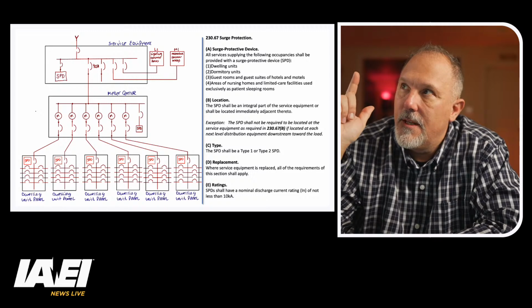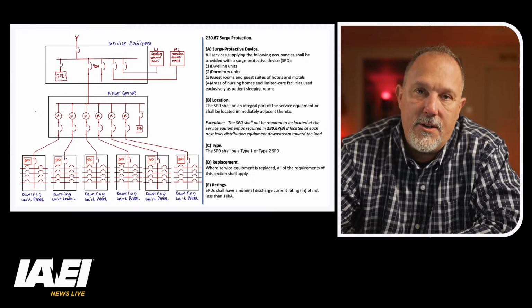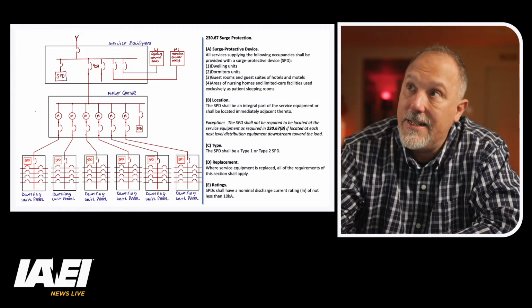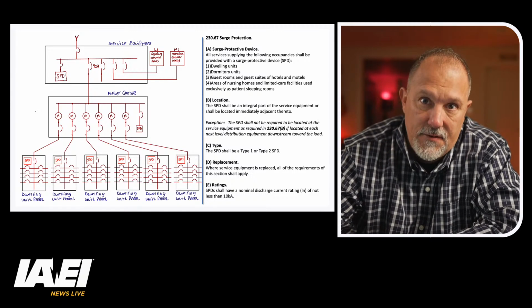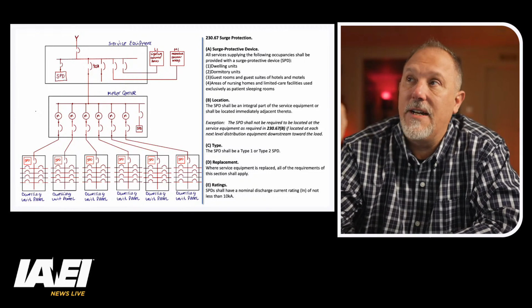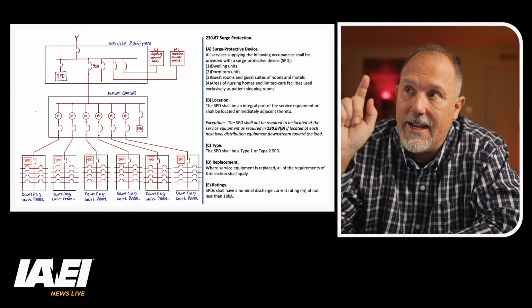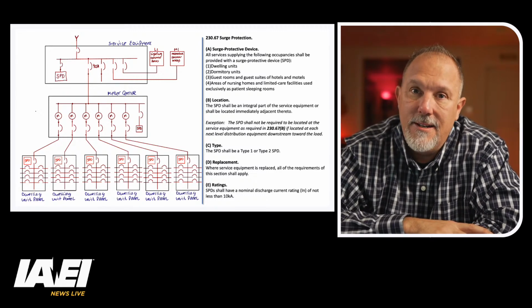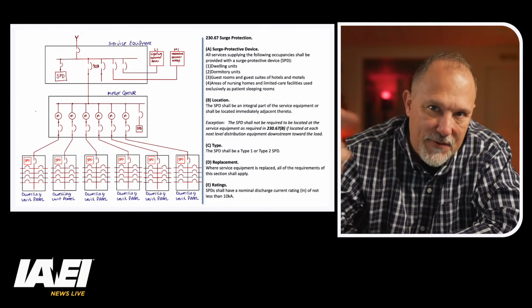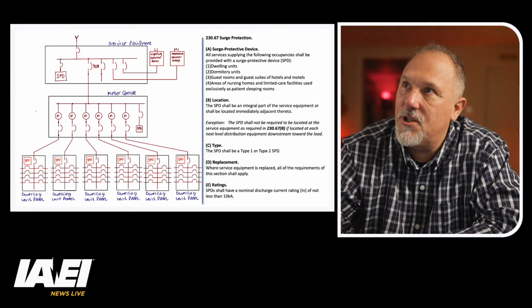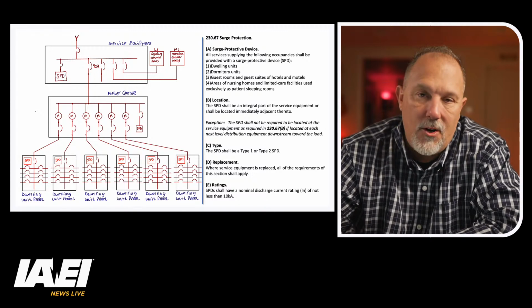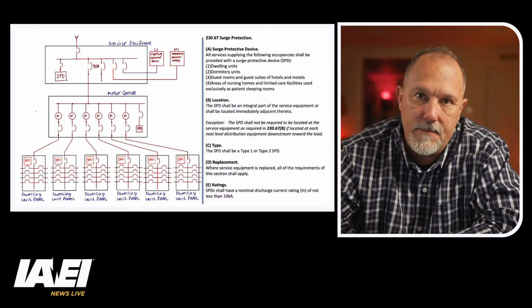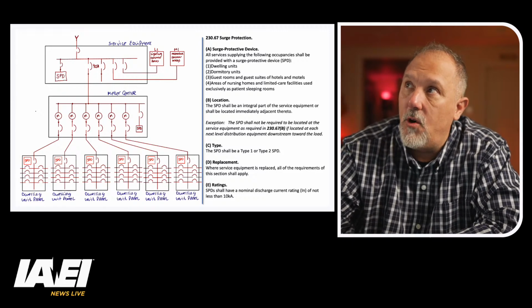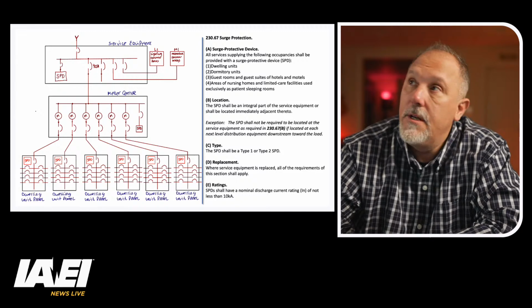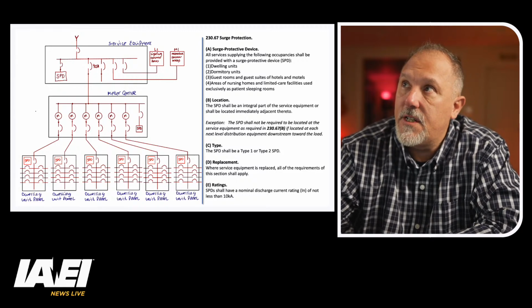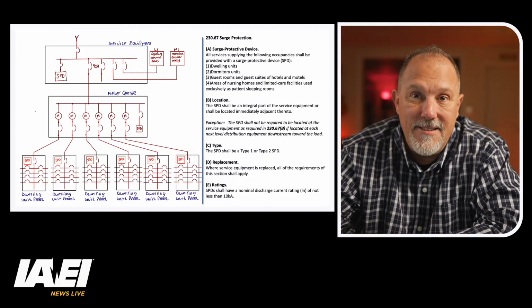So those L1 and M1 did not have surge. So what this group did was not put a surge protected device in the service equipment, and they did not put a surge protected device in the meter center. They only put surge at each of the dwelling units, which violates two sections in two different articles. 230 would require surge in the service equipment because the L1 and M1 panel does not have surge. If they put surge in L1 and M1, which probably would have been easier, I don't know, then you wouldn't need it in service equipment if you also had it in the meter center.